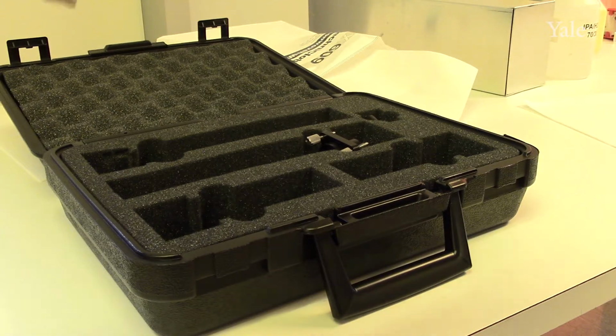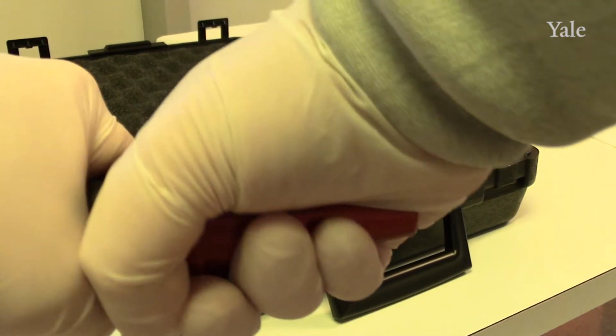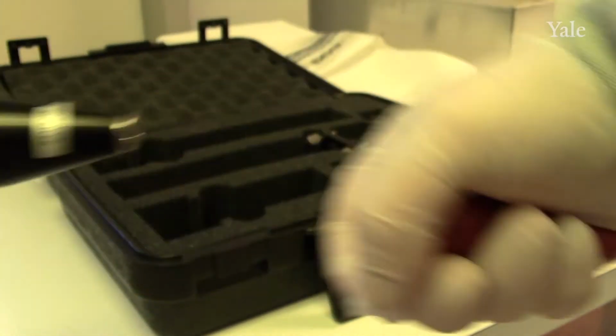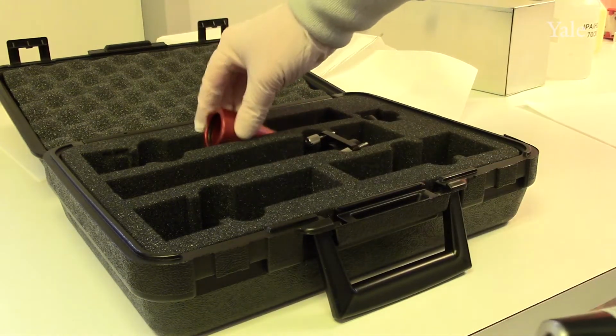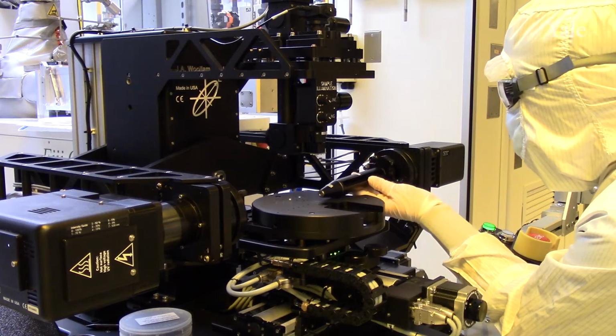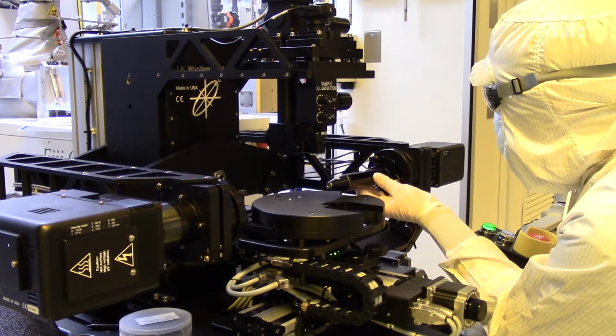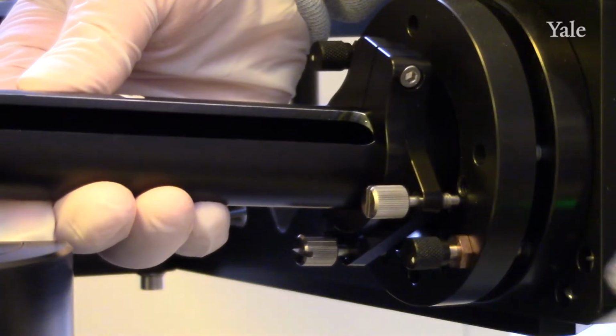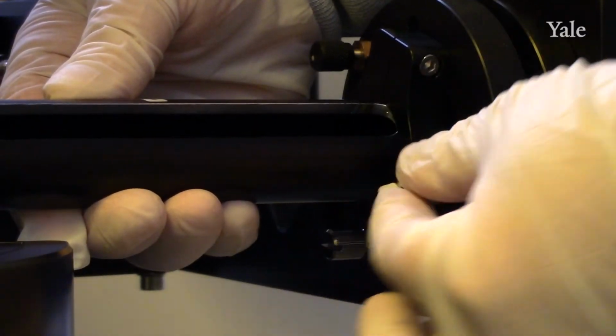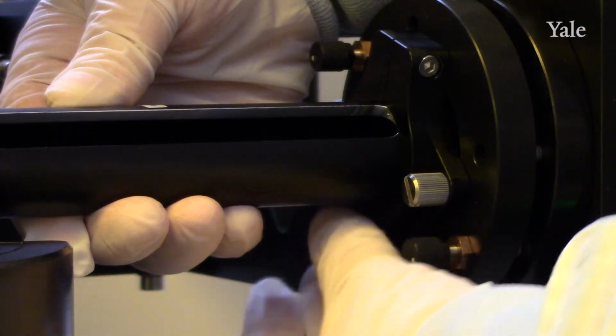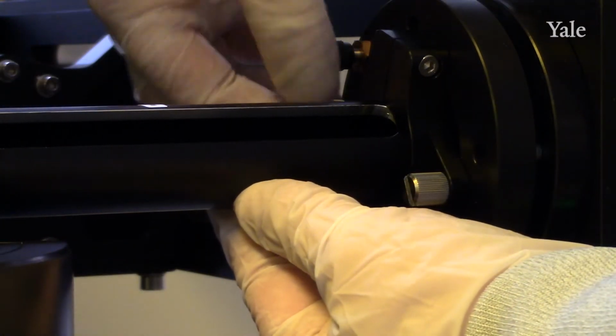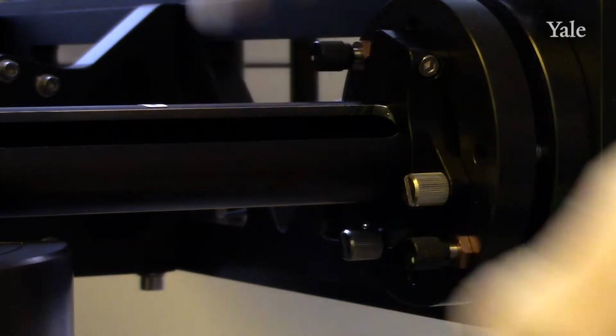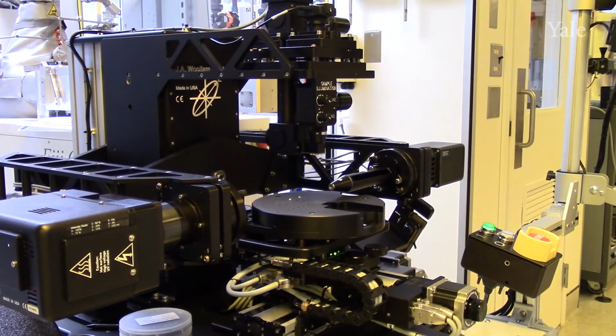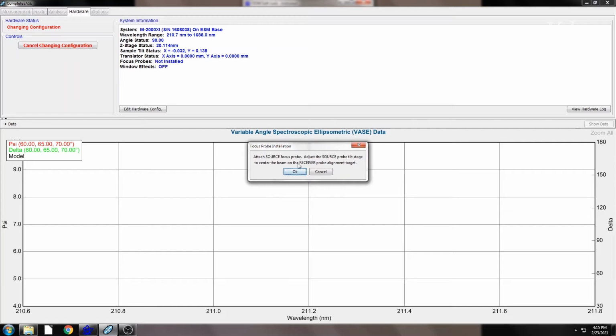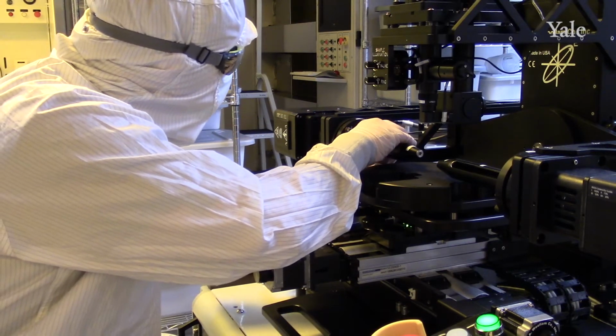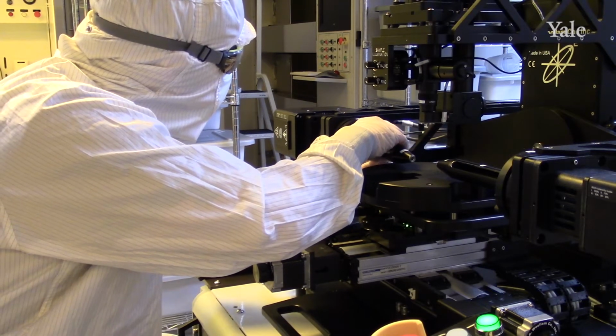Take the receiver probe and carefully remove the protective cover by pulling while gently twisting back and forth. Place the cover back inside the foam case. Once the cover is removed, take the probe and align the 3 thumb screws with the ellipsometer's receiver and carefully tighten them. Press OK, and the software will prompt you to attach the source probe. Repeat the same steps as you did with the receiver probe, but on the source side of the ellipsometer.